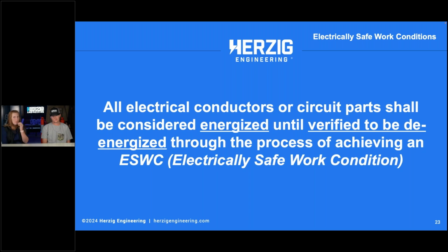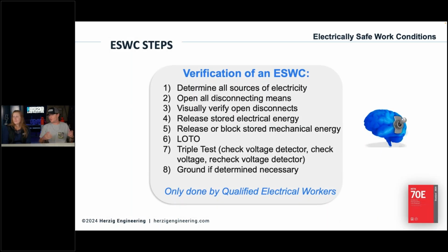Let's briefly summarize electrically safe work conditions. Step 1 of verifying an electrically safe work condition is determine all sources of electricity. Number 2 is open all disconnecting means. Number 3 is visually verify the open disconnects.